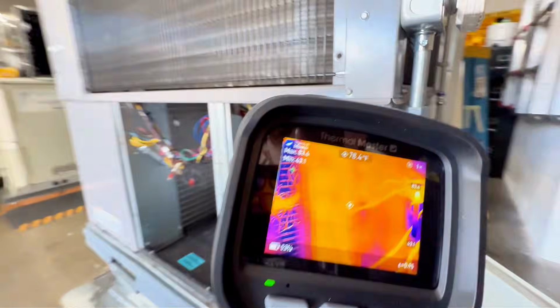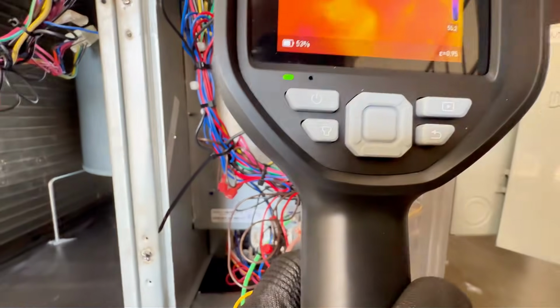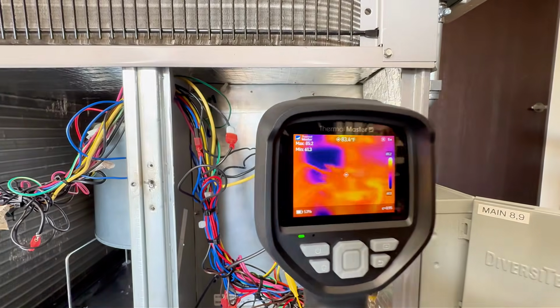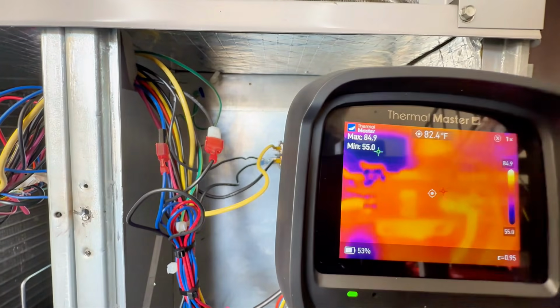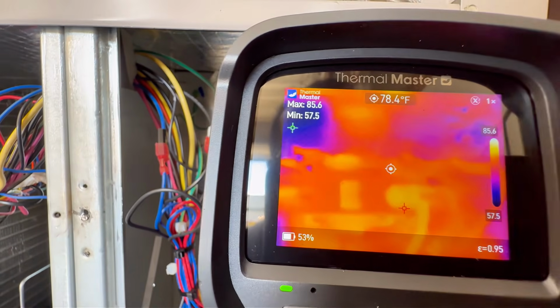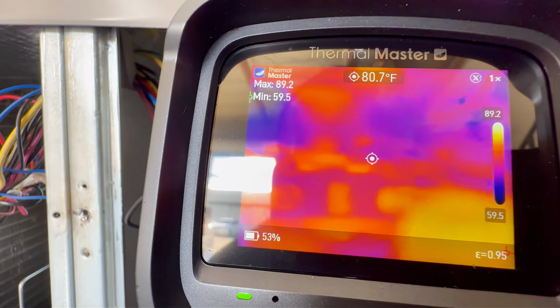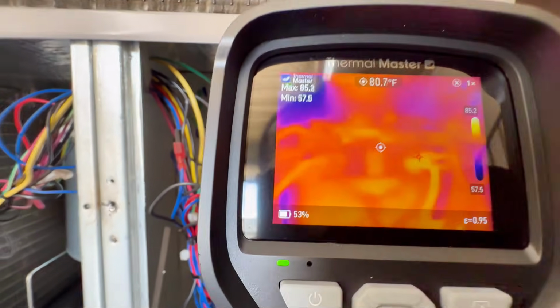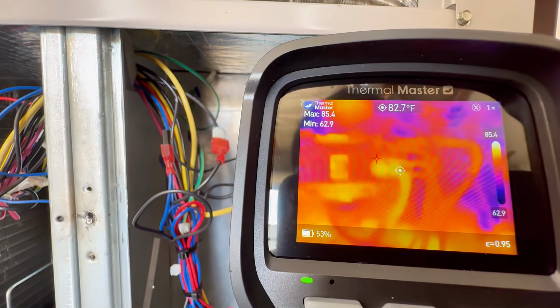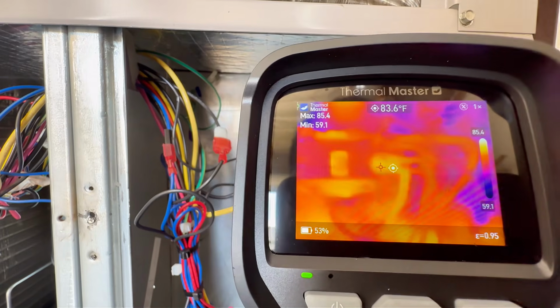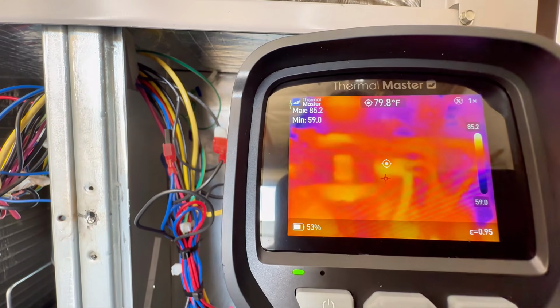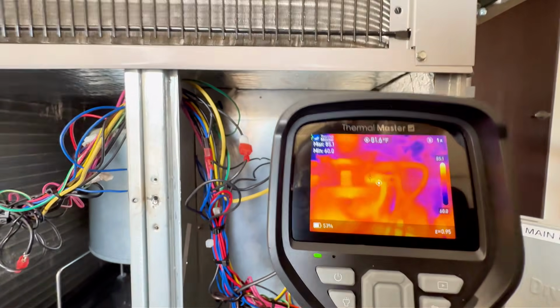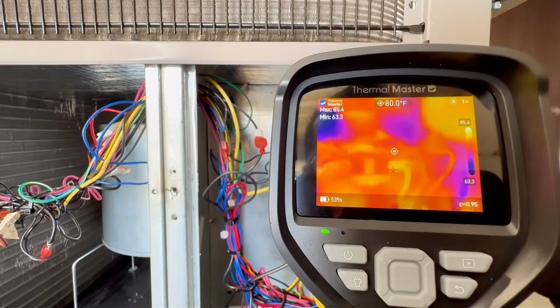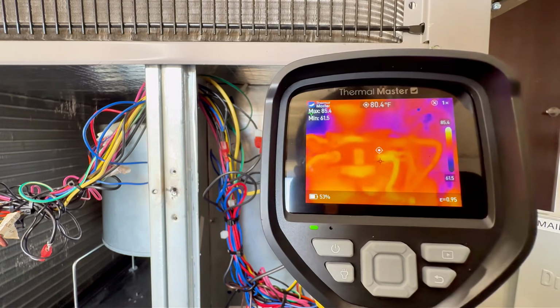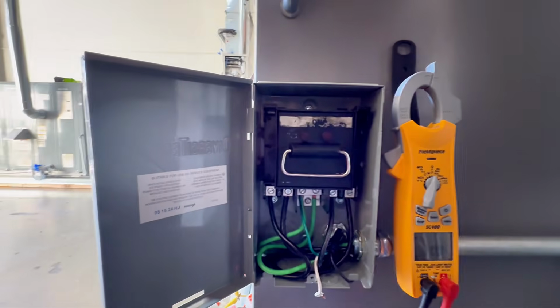Look at this over here now. Look at this contactor. Okay. Let me get it here situated. Okay, let's see. So we're checking for, there we go. You see the wire on the bottom right. You see this right here? Right, this is where my finger's at. That's the wire that's loose. So you see that? You see how it's a little bit more orange than the wire on top? Because it's loose. There's resistance. Current is making more of an impact. And so it's such a simple thing that you can do to avoid, right? It's just by simply checking that it's tight enough, okay? So the way you would fix it, let's go ahead and turn this off.